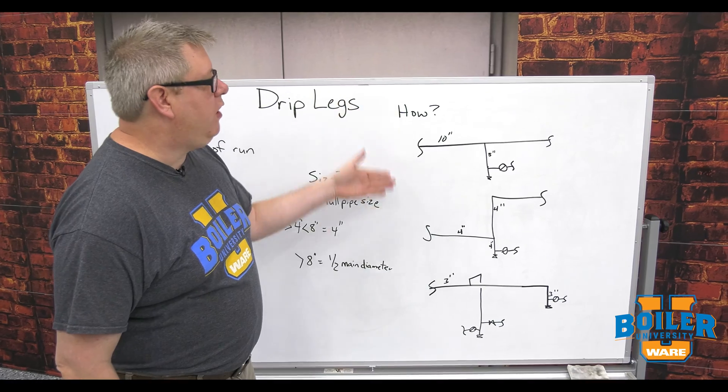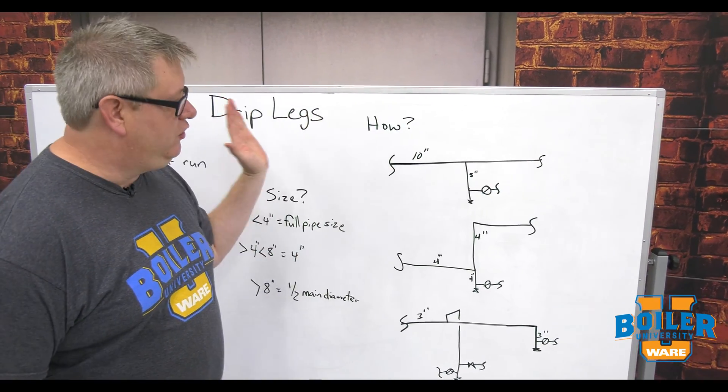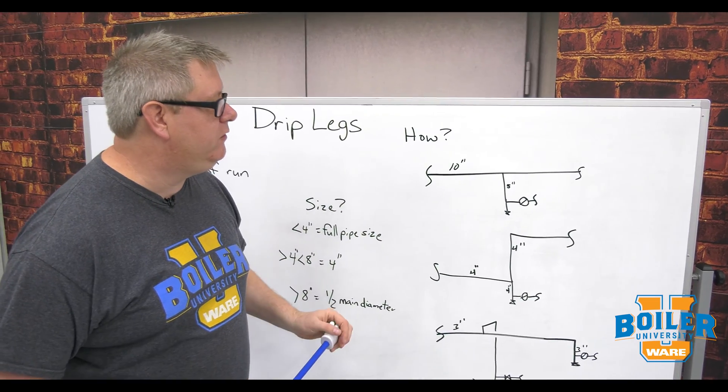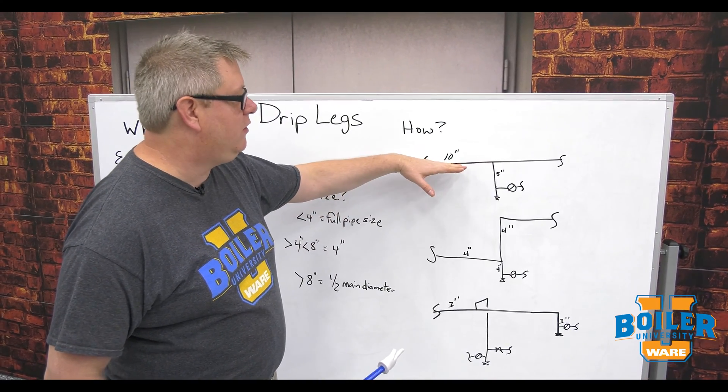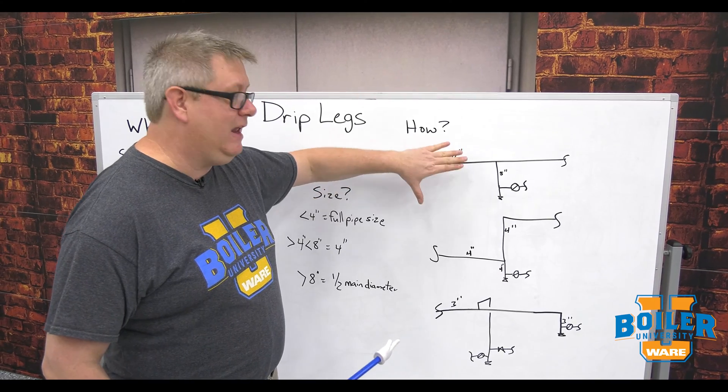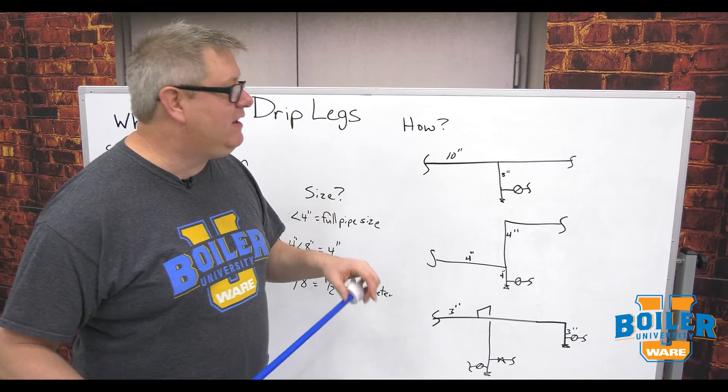So how are we going to install the drip legs? If I've got a horizontal run, one of those 200-foot interval portions, I'm going to look at my main line size. In this case it's 10 inch, so I'm not going to use a 10-inch drip leg, but I'm going to use half of that diameter.